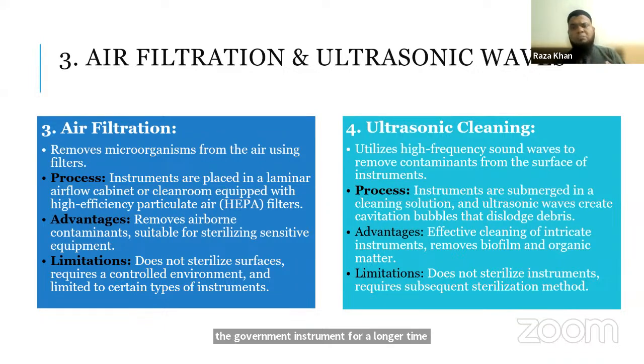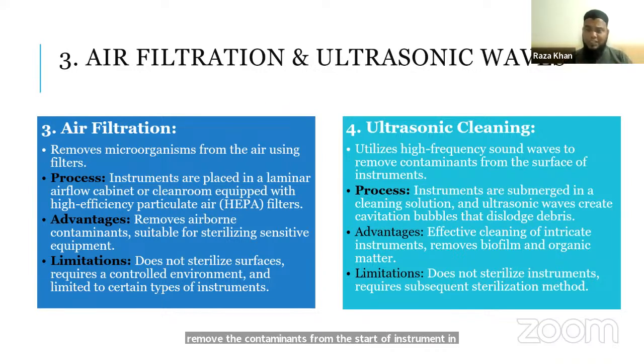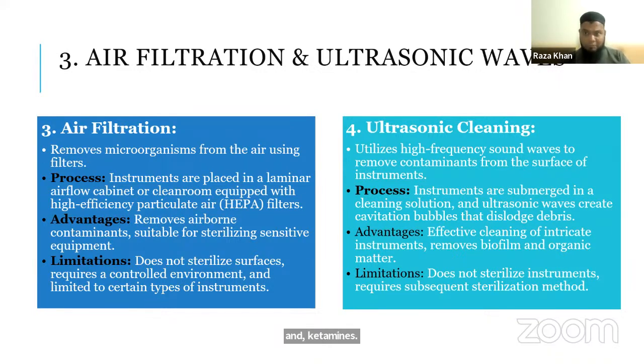The ultrasonic wave method is usually used for disinfection and cleaning of delicate instruments. In this method, high frequency sound waves are used to remove contaminants from the surface of the instrument. Instruments are submerged or dipped in cleaning solution, and ultrasonic waves create cavitation bubbles that dislodge germs and contaminants. That is an effective way of cleaning delicate instruments and micro instruments, and it also removes biofilm and organic matter.